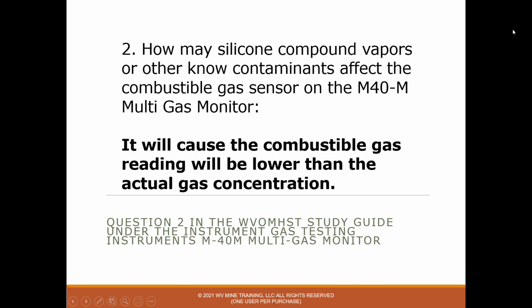Question 2, how may silicone compound vapors or other known contaminants affect the combustible gas sensor on the M40-M multi-gas monitor? We've already had a question like this. When you see silicone compound vapors, hopefully you remember that, you're looking for lower. So the answer is it will cause the combustible gas reading to be lower than the actual gas concentration.